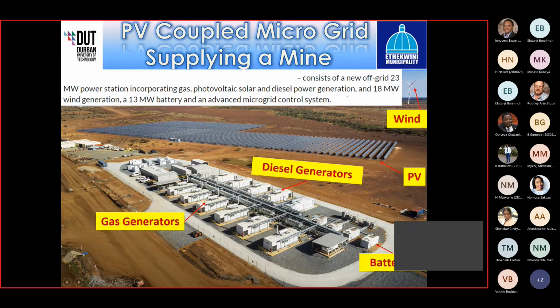So PV systems can be coupled with other sources of energy, such as this example where it's used in a microgrid situation to feed a mine. Obviously, this is not in Durban, but you can see that it consists of a 23 megawatt power station incorporating gas generators, a large PV system or PV farm here, diesel generators, 18 megawatts of wind, and a 13 megawatt battery and an advanced microgrid control system. So you can see this is a typical standalone system where it's not dependent on the grid.